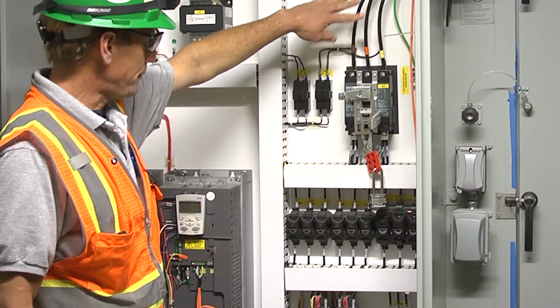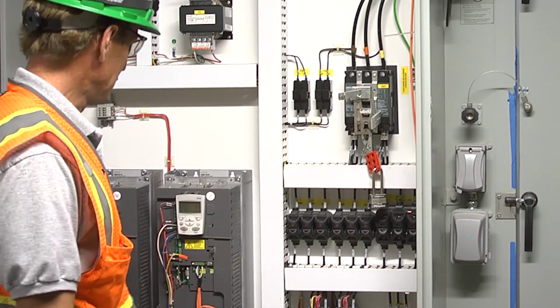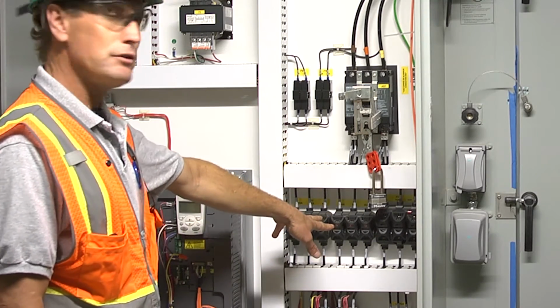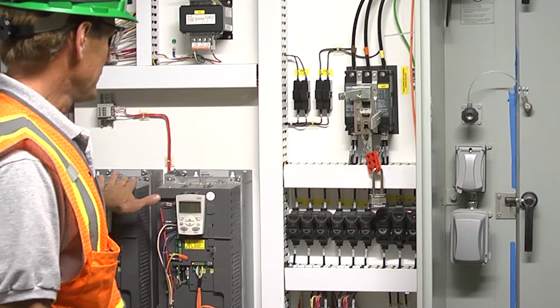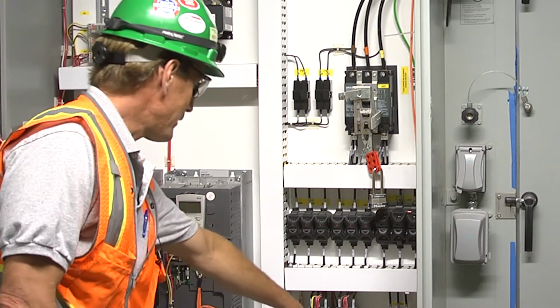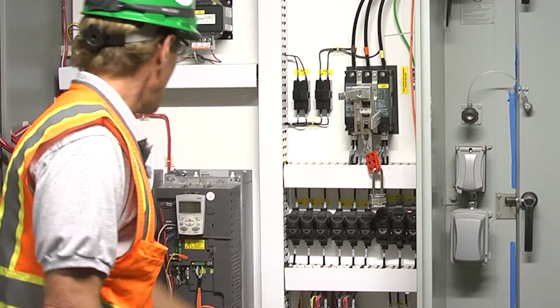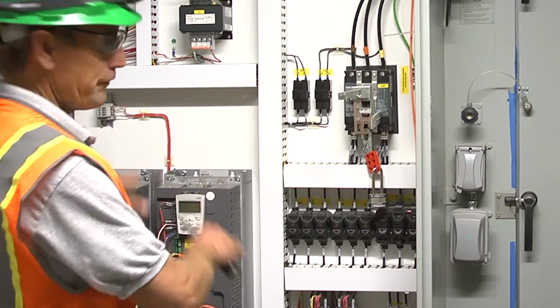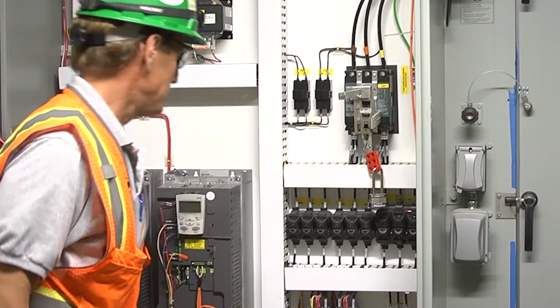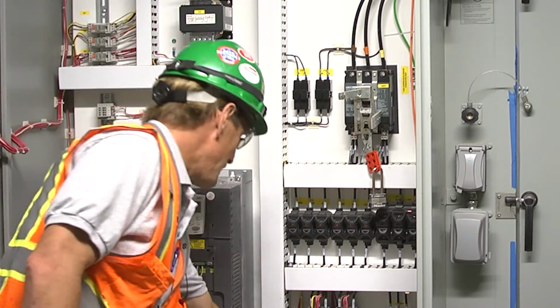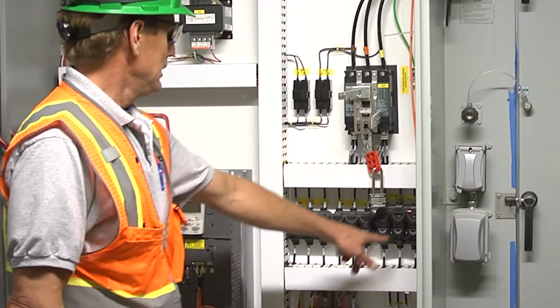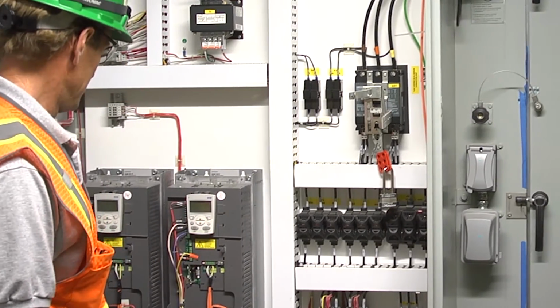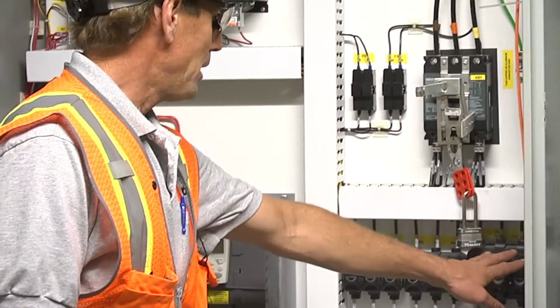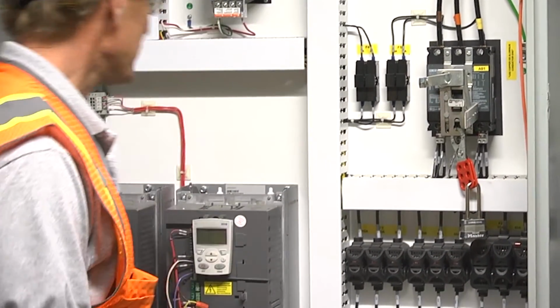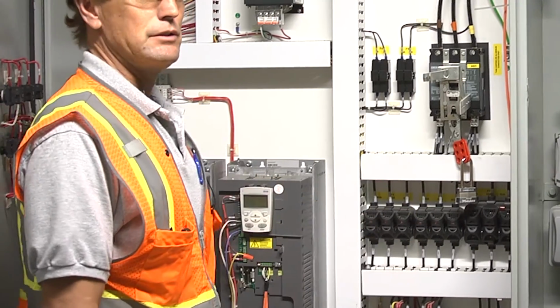So concerning the electrical lineup, again, here's our three-phase 460 coming in here, goes through the molded case switch. Then we have load side fuses that are before the VFD, and then leaving the VFD, we have mechanically interlocked contactors, so that both VFDs can't run at the same time. So they're interlocked between those two contactors. And then further, on the load side, we have a circuit breaker and a fuse for all 4 motors. So the motors are protected by this set of fuses and those circuit breakers. The drives are protected by these fuses here.